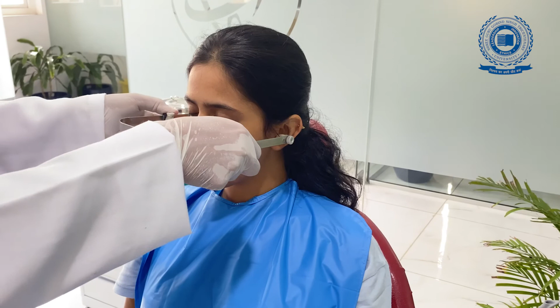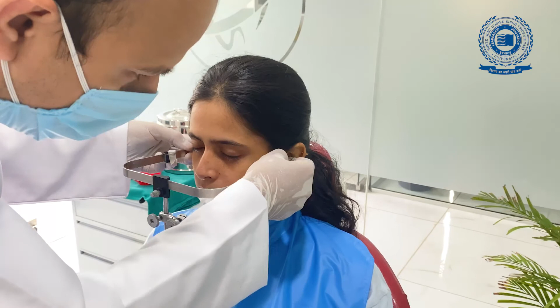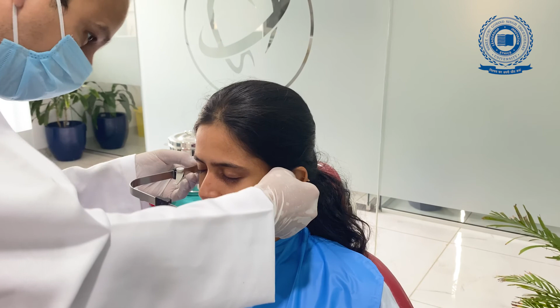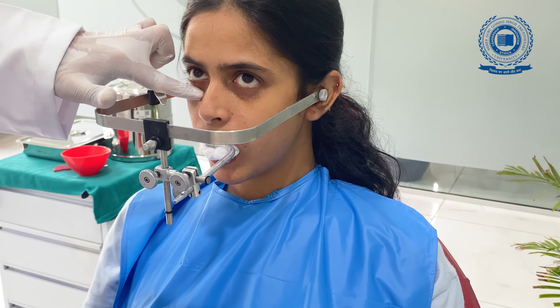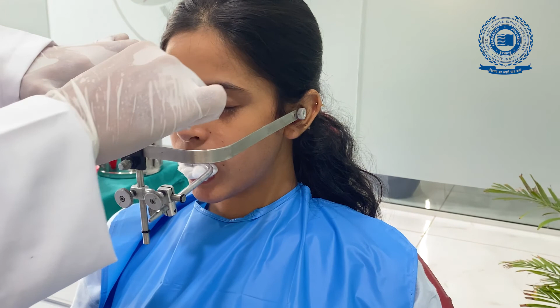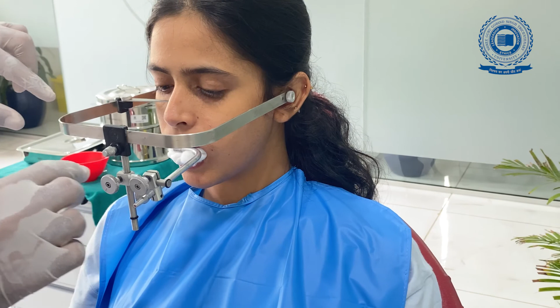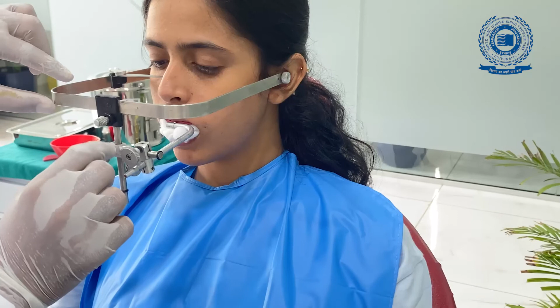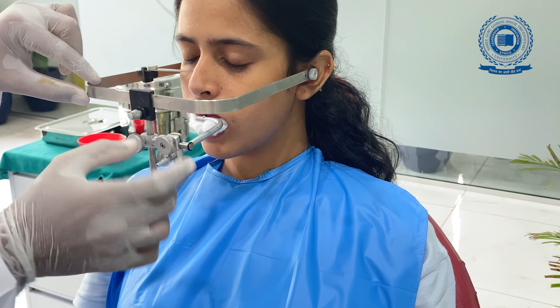Then insert the condylar rods of the U-shaped frame in the external acoustic meatus of the patient very gently. Then locate the infraorbital notch and match it with the orbital pointer of the facebow. Then tighten the 3 screws of the locking device. First tighten screw number 1. Then screw number 2. And then screw number 3.